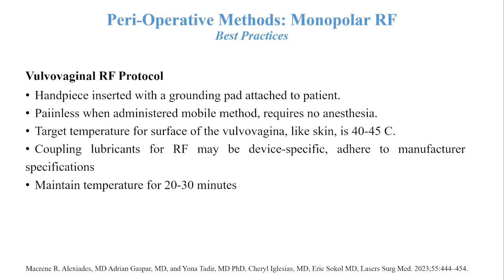I had discovered that if we keep the skin surface temperature 42 degrees or below, that obviates the need for anesthesia. It doesn't trigger your C and A-delta afferents of pain, but also prevents burns. So that mobile delivery is what is used typically for vaginal treatments, and the target temperature we set on our devices is between 40 and 45. And then in coupling lubricants, we use aqueous gel. Maintain the temperature for 20 minutes.